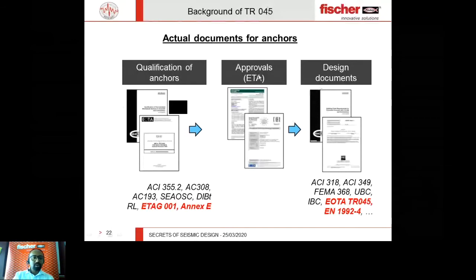One important qualification is that any anchor can be a seismic anchor only if it is designed to work in cracked concrete, meaning non-cracked concrete anchors are normally not qualified for seismic purposes. Another requirement is approvals: the anchors should have a valid ETA approval or an ICC approval. If following ACI standards, the anchors must have an ICC (International Code Council) approval. If following European standards, it should have a European Technical Assessment document.